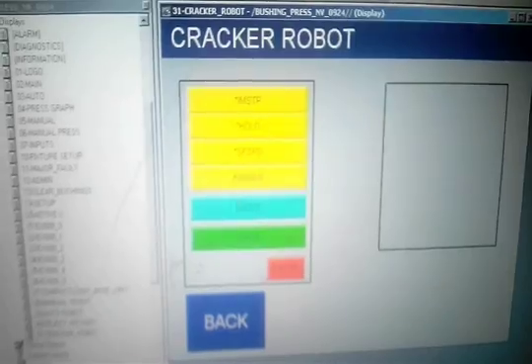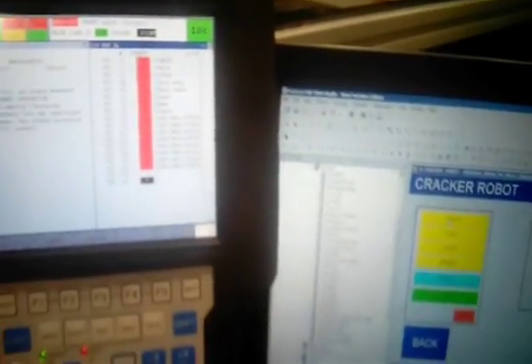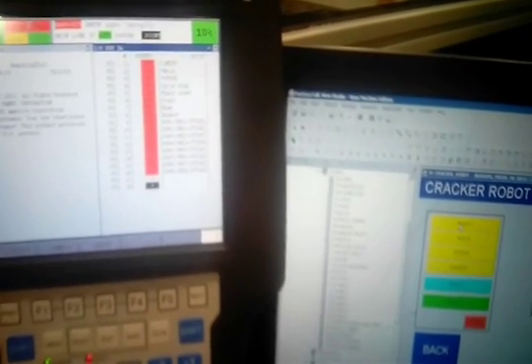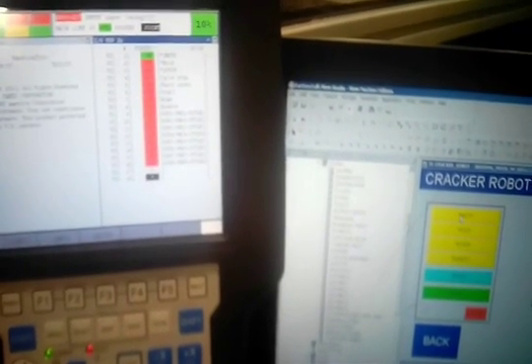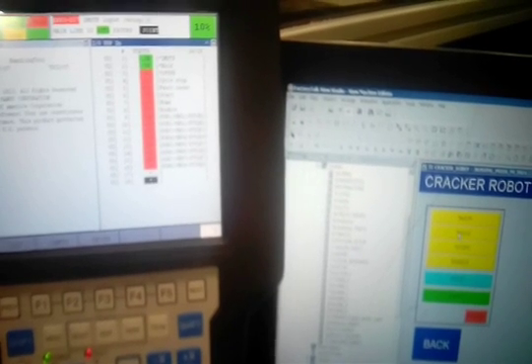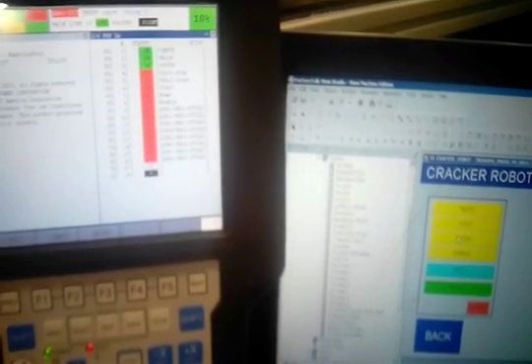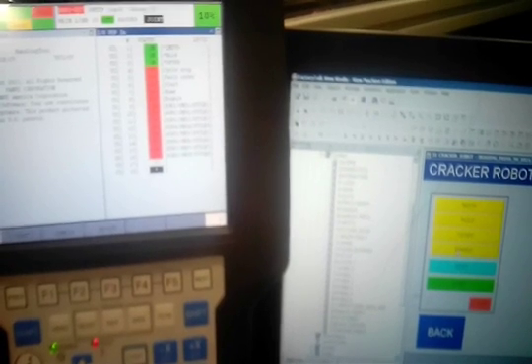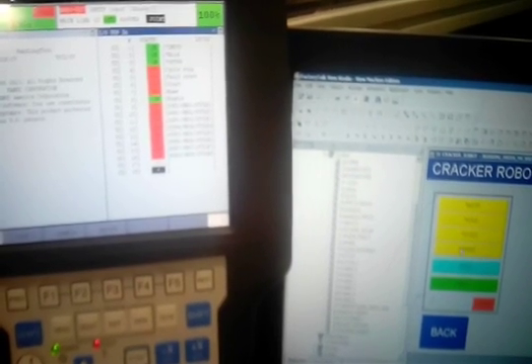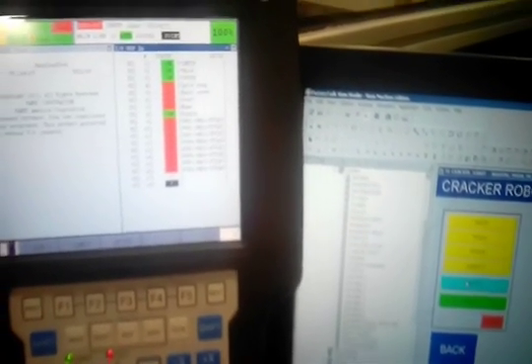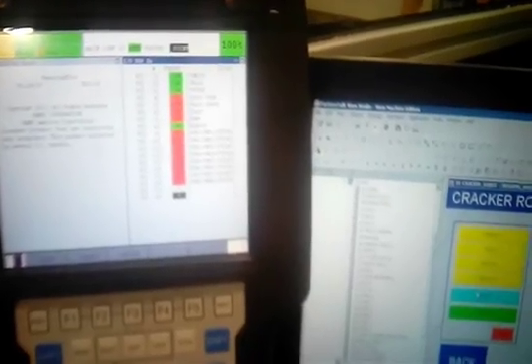So now the robot dual check safety is remotely enabled by the Control Logix PLC. Control Logix is a scanner. Robot is an adapter. So I'm enabling the immediate stop, hold, safety speed and the enable signals. Those have to be set to one and then press reset. That's what I'm doing here. Enable. Press reset. And you can see the response on the teach pendant.